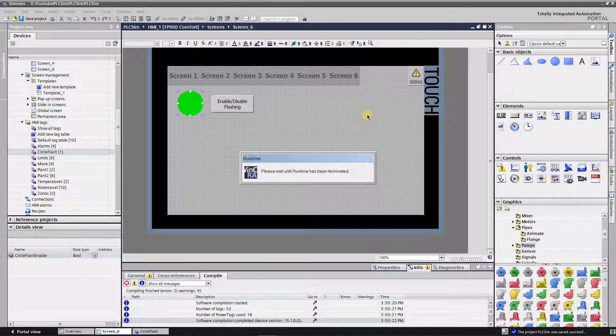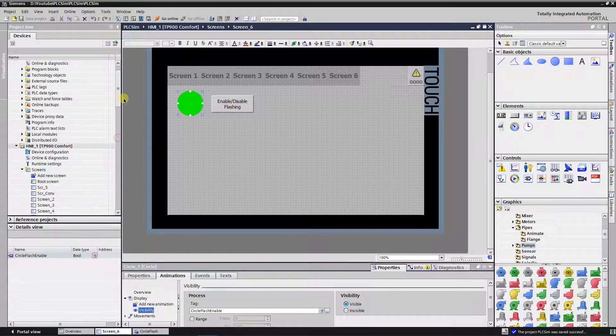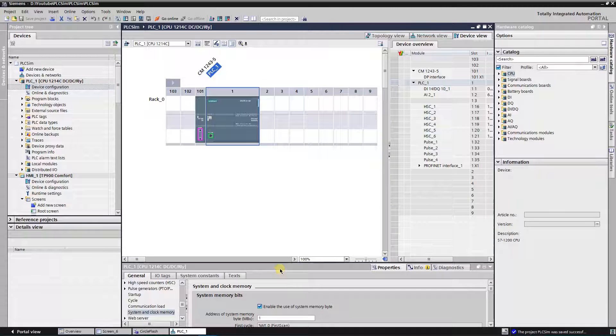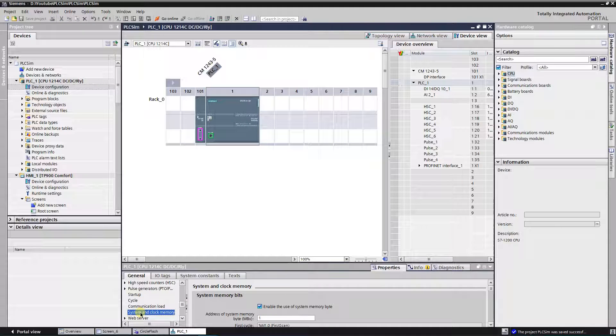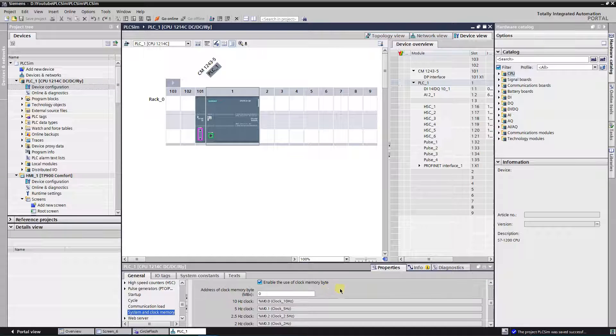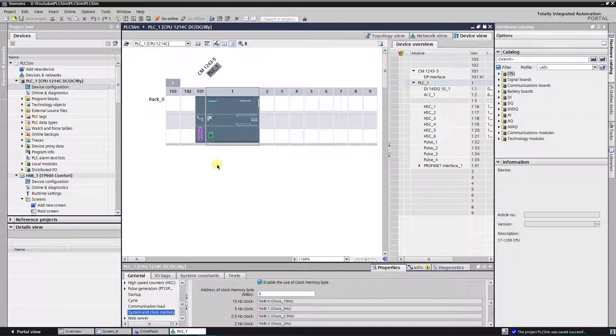Let's go more advanced. Instead of static flashing, let's use a tag from the PLC. Siemens PLCs have a memory area where 8 bits of different frequencies are stored — it is called clock memory. It needs to be activated in the properties of the CPU. Open the hardware configuration of your CPU. Find system and clock memory under the general properties. Tick the check mark to activate the clock memory byte. By default it is MB0, but you can change it to any value suitable for you.